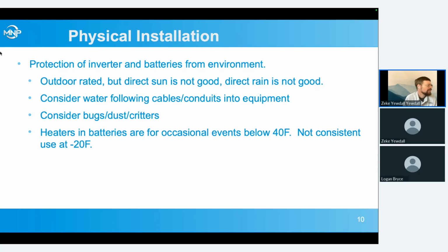I got some questions on the heating here. If the batteries are just turned off and stored, so the battery BMS is turned off, not just the inverter turned off, because it's still pulling some current then, I believe that would be okay if the batteries are stored at low temperatures. Logan can chime in on that perhaps.